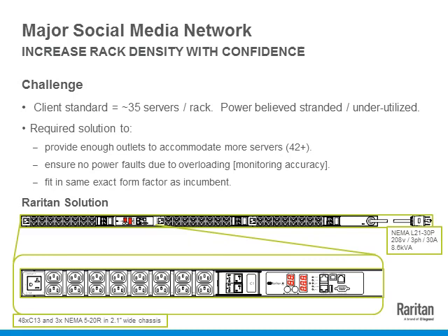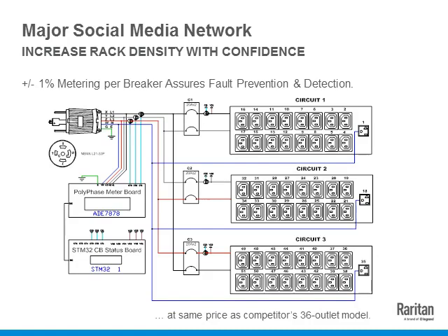So this is the social media company, the case study that we have, where you'll see there's a reason why we have put much emphasis on metering accuracy and on the monitoring in this particular case. When we load 40 servers in a single rack, but keep the capacity still at 8.6 kVA, there is very little headroom left for any kind of unexpected peak loads.